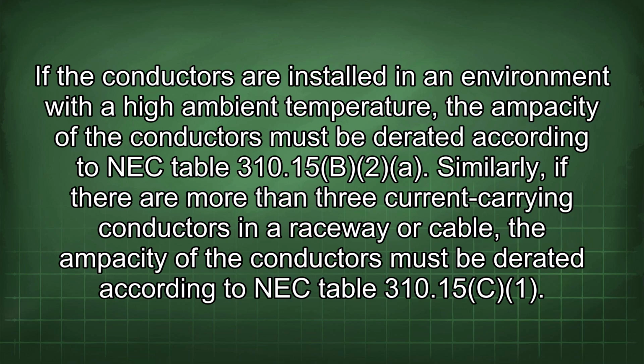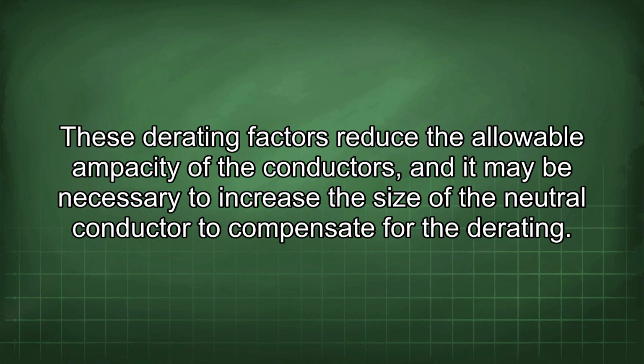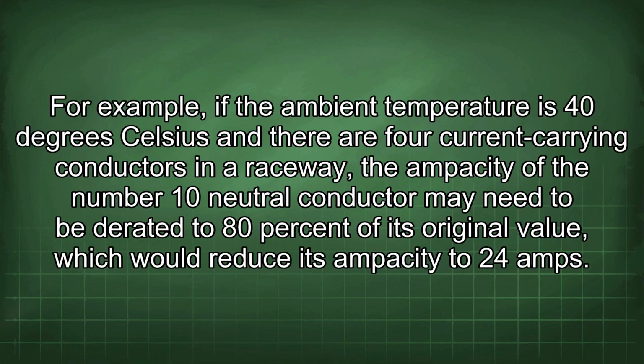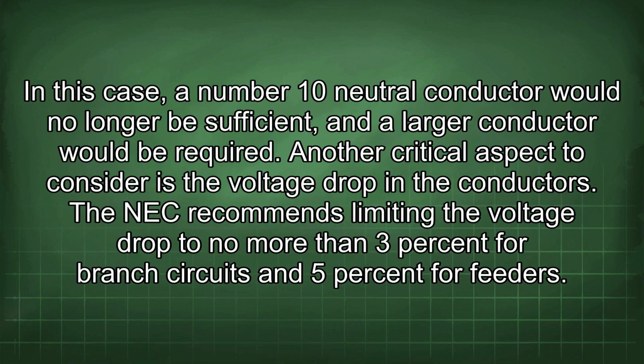Similarly, if there are more than 3 current-carrying conductors in a raceway or cable, the ampacity of the conductors must be derated according to NEC Table 310.15(C)(1). These derating factors reduce the allowable ampacity of the conductors, and it may be necessary to increase the size of the neutral conductor to compensate for the derating. For example, if the ambient temperature is 40 degrees Celsius and there are 4 current-carrying conductors in a raceway, the ampacity of the number 10 neutral conductor may need to be derated to 80% of its original value, which would reduce its ampacity to 24 amps. In this case, a number 10 neutral conductor would no longer be sufficient, and a larger conductor would be required.